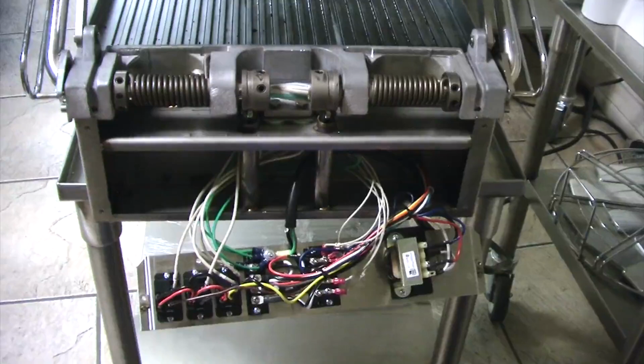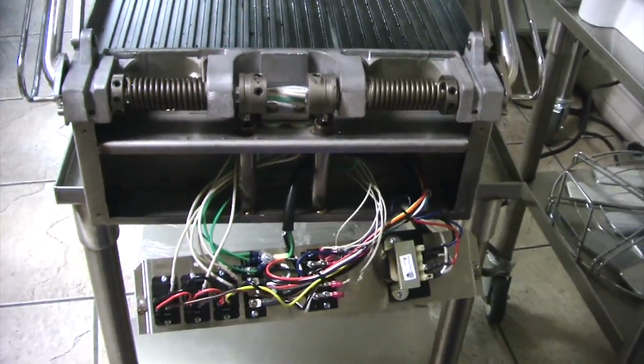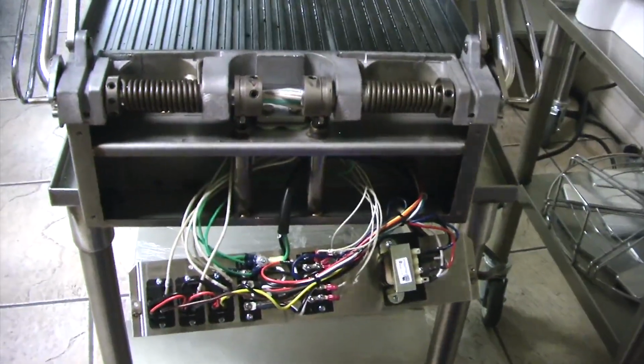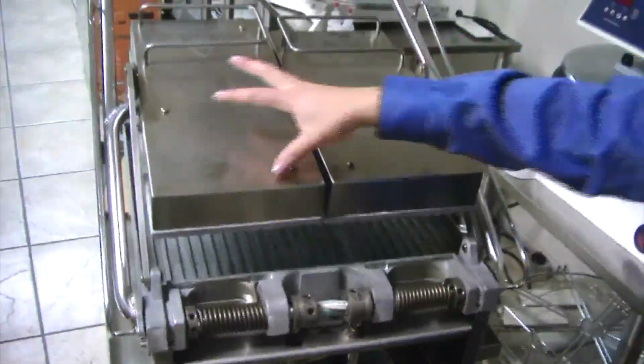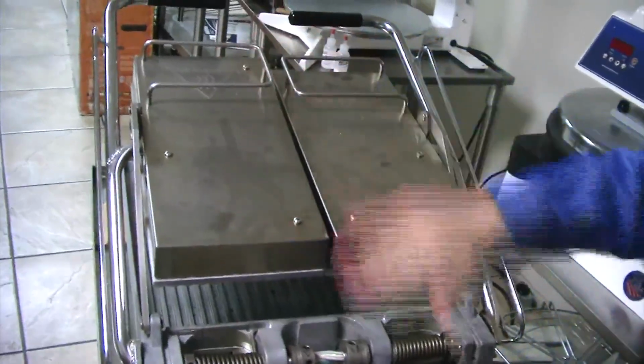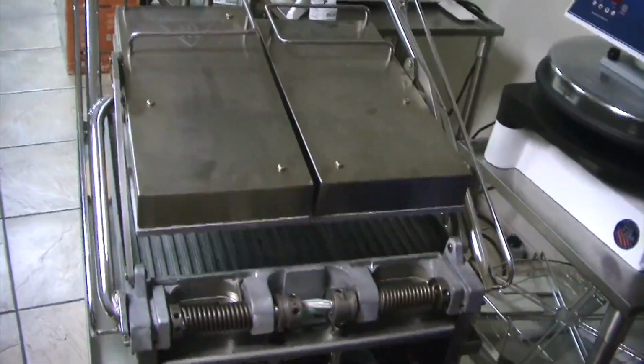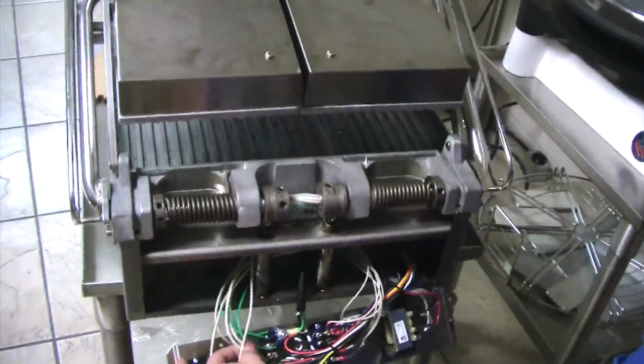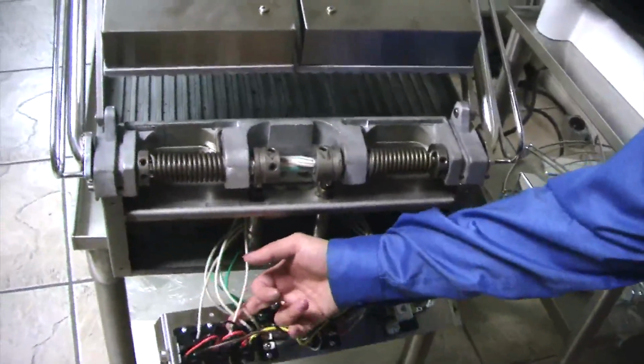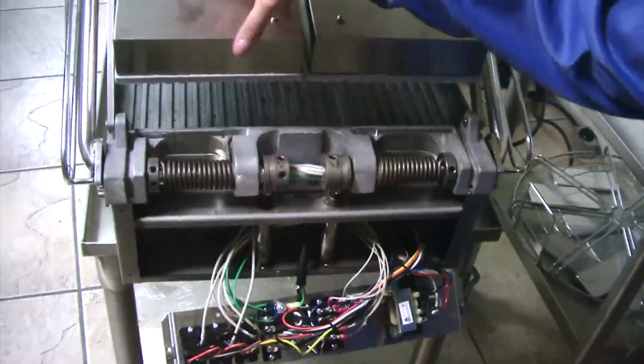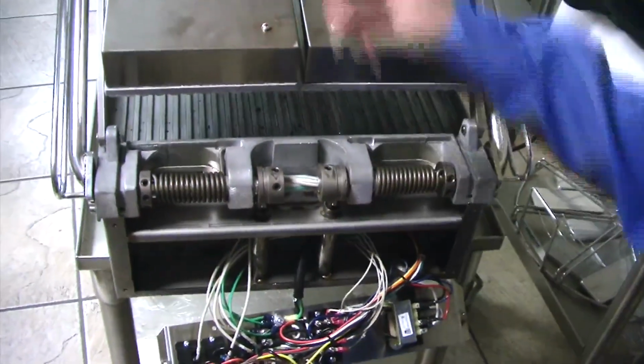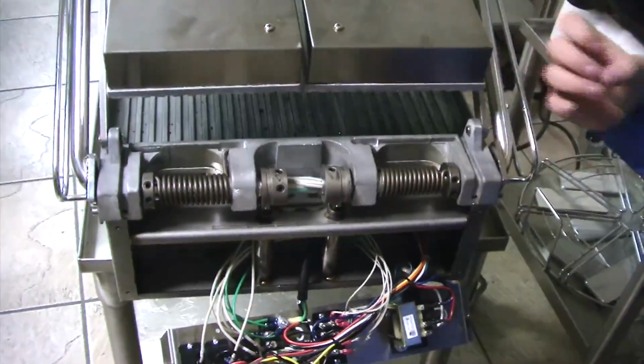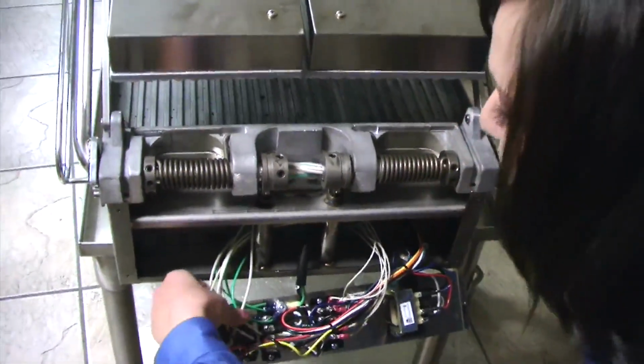So what you would need to do to get the correct reading from the element itself is take off the shroud by the screws on the top. If it's one of these, you want to take off the shroud by the screws and take out the insulation. You're going to see your heater wires. You can't check the platen for continuity based on these wires. A lot of times, I've taken apart the platen just to find that the wires are actually burnt off the element and that continuity is still there. It's still good.